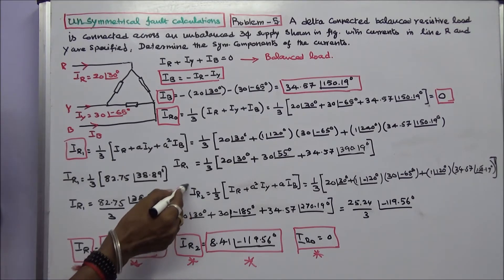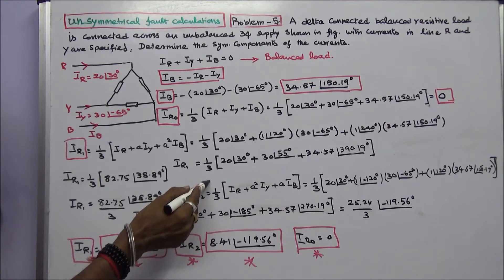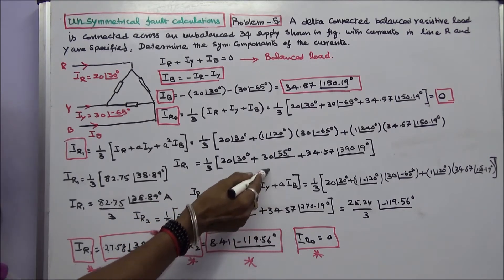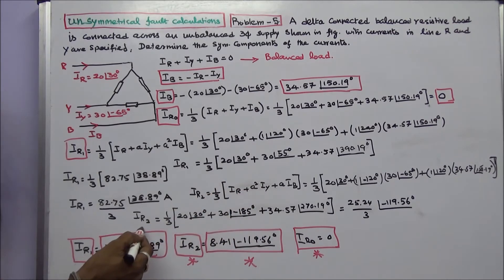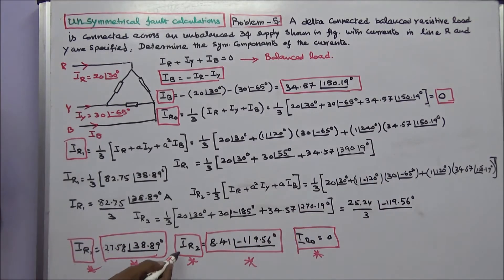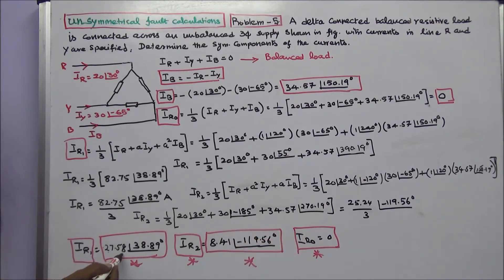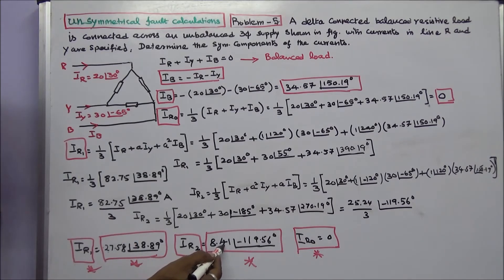Next is IR2. IR2 is equal to 1/3 into IR plus A²·IY plus A·IB. Substituting all values, IR2 is equal to 25.24 divided by 3 angle minus 119.56 degrees, therefore IR2 equals 8.41 angle minus 119.56 degrees. Summary: IR0 equals zero, IR1 equals 27.58 angle 38.89 degrees, IR2 equals 8.41 angle minus 119.56 degrees.